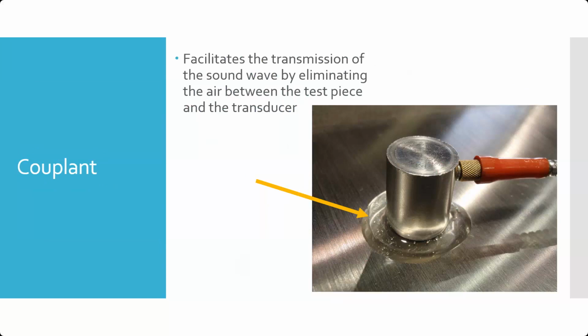And so we don't want to have all those little air pockets. All those little air pockets will attenuate the sound, make it so that we don't get as good of a signal. We'd have to turn our amplification up really high, and that would cause a lot of distortion, and it would cause a lot of interference that would make it hard to use. So we put this couplant here, and it acoustically bonds the two of them.